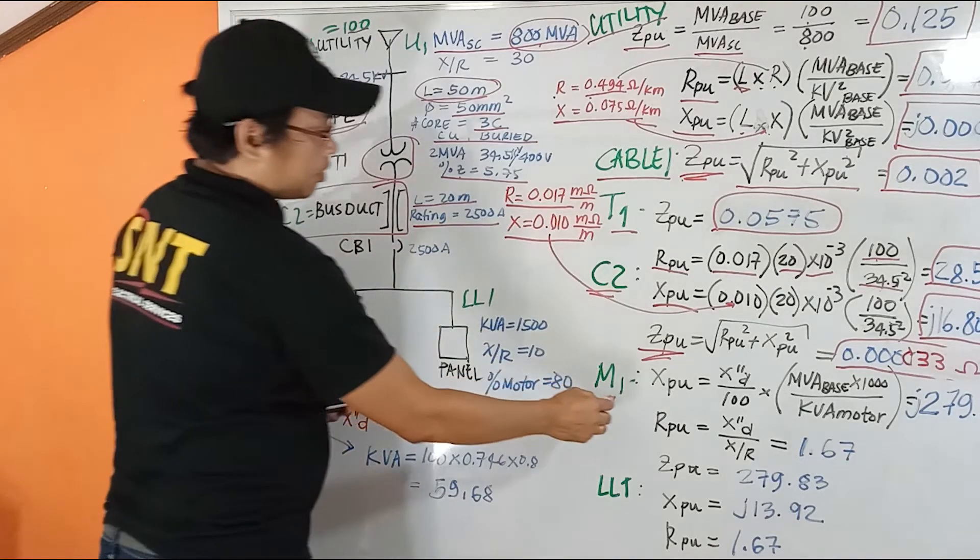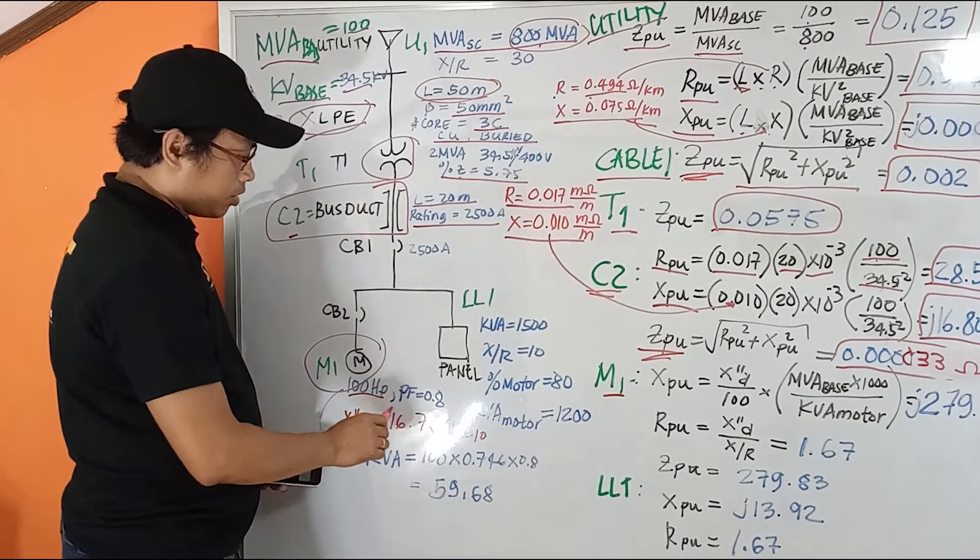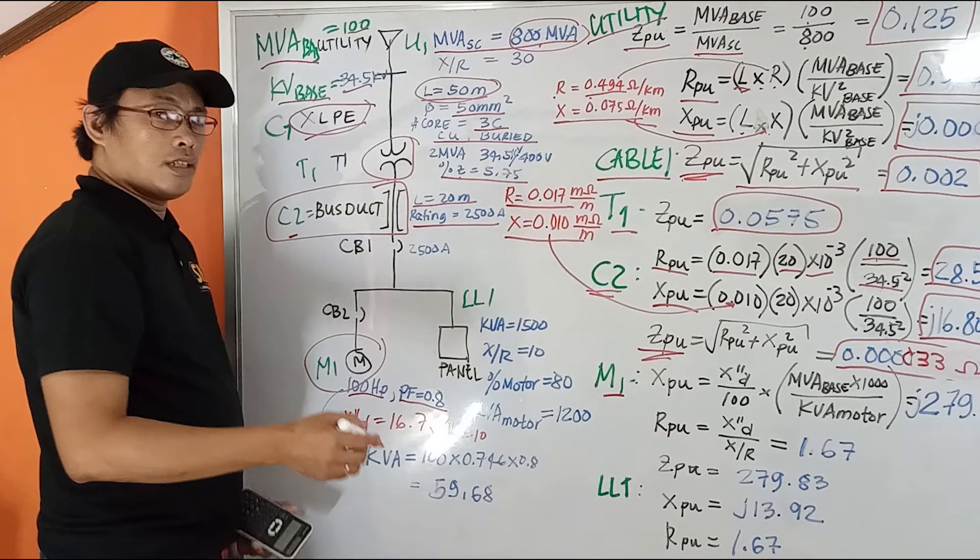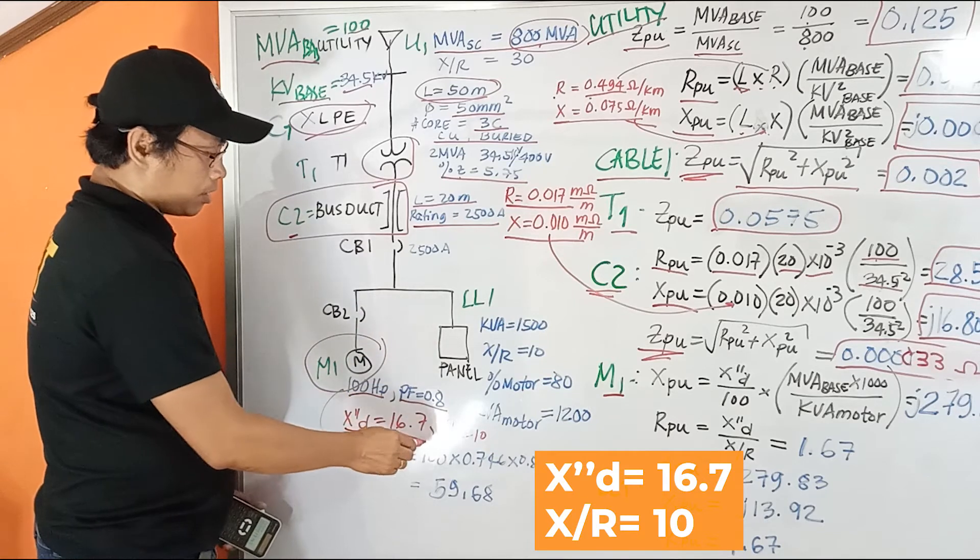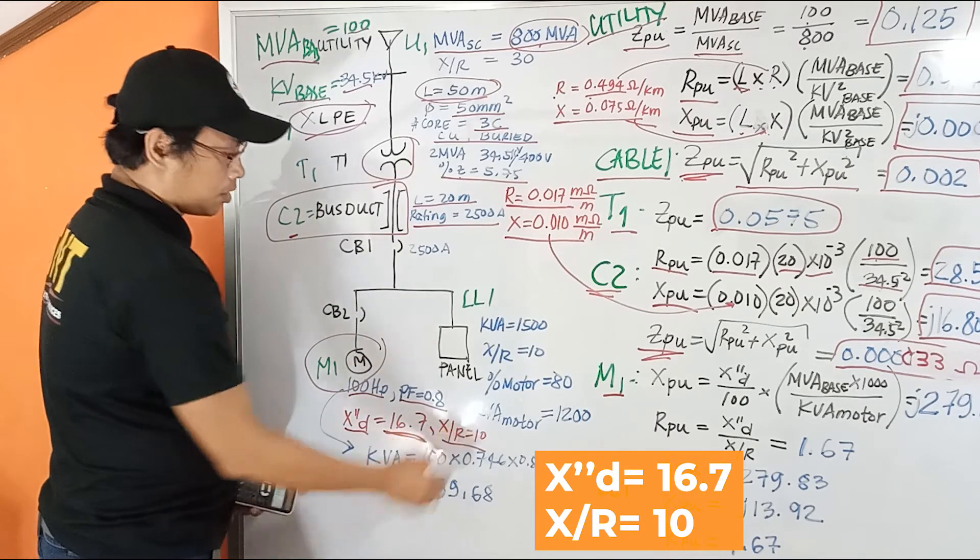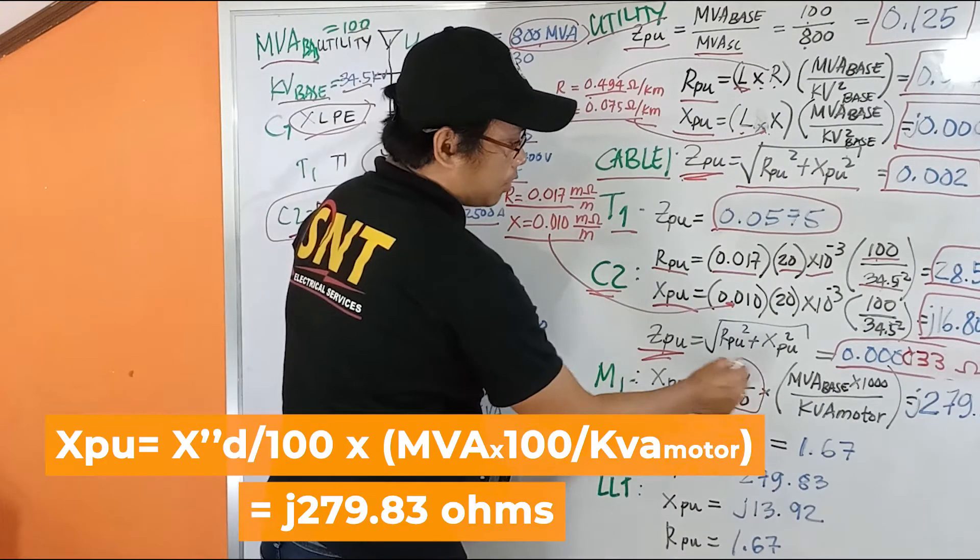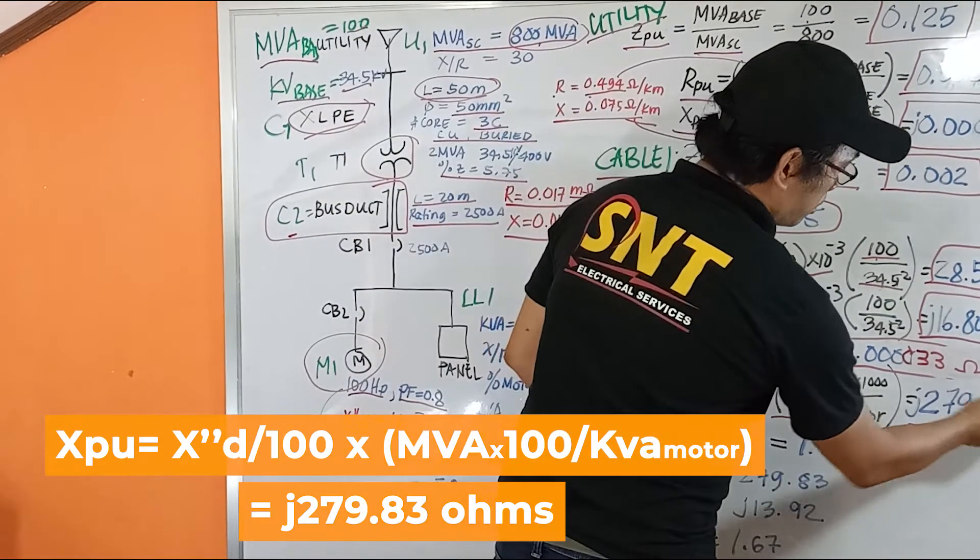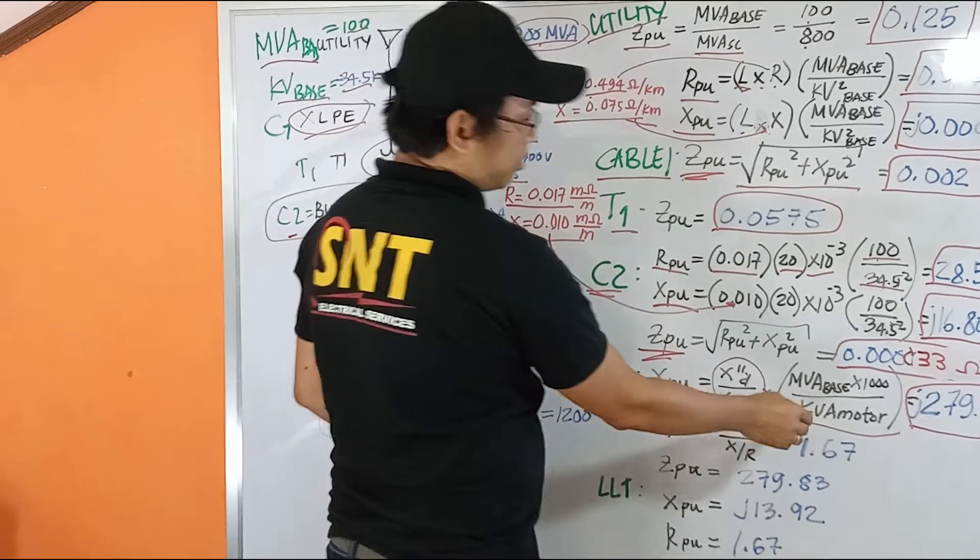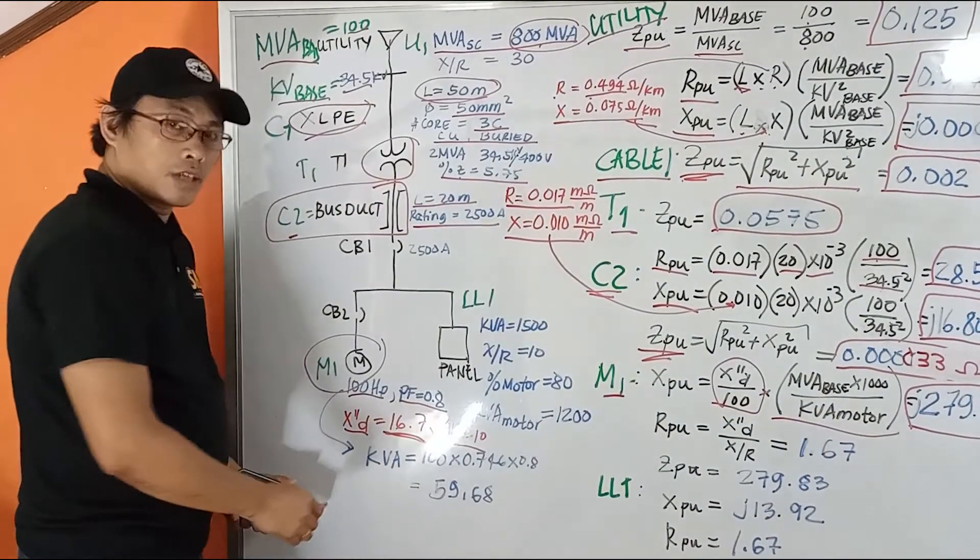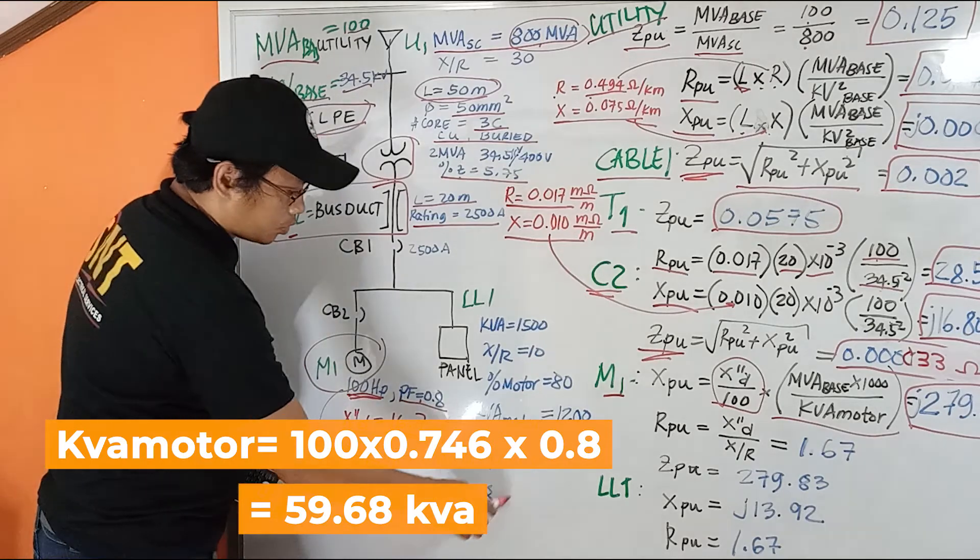Then we calculate our motor M1. Motor M1, given 100 horsepower, power factor of 0.8. Now, upon getting the sub-transient impedance from the table, from the standard, we assume at 16.7, and X over R is 10. So substitute it in the formula here. And our result is this one. 16.7 divided by 100 times MVA base, which is 100 divided by MVA motor. So our calculation is to get the MVA of the motor.